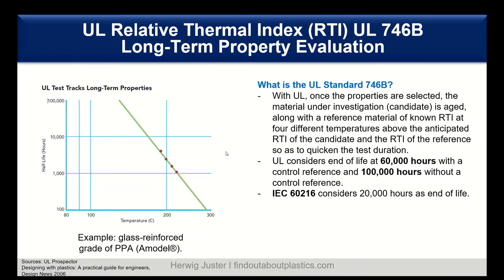What more is there to say about UL 746B? In general, UL considers end of life at 60,000 hours — in combination with a control reference — and 100,000 hours without a control reference. This is what is meant by the extrapolation. In comparison, the IEC 60216 considers only 20,000 hours as end of life. So it is quite an important property in plastics part design to have both a short-term and a long-term property evaluation.